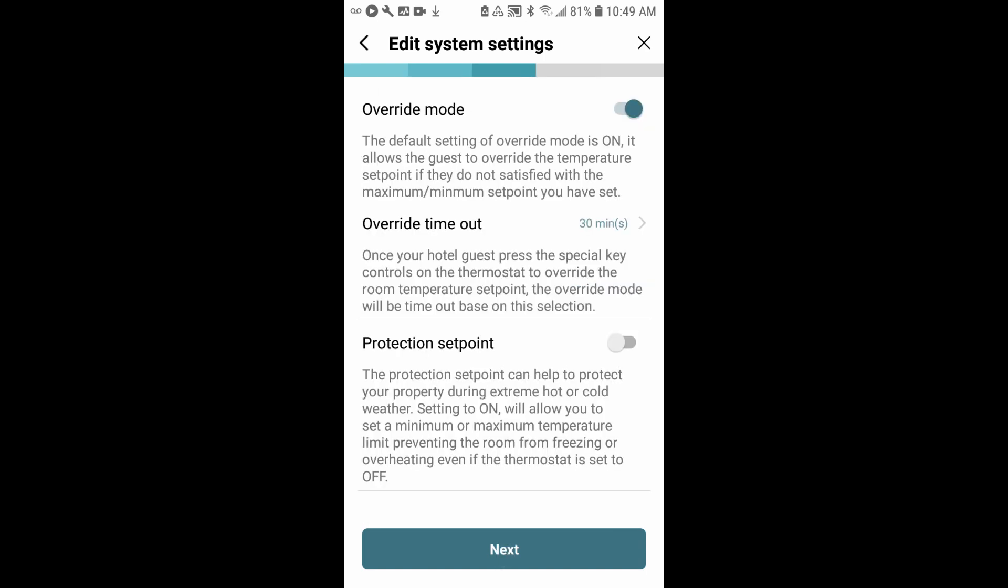Override mode is if you happen to have your temperature threshold set very tight - say that you'd set it 78 degrees and the guest wants it to 80 degrees - an override mode will allow them to press and hold an up or down arrow key to adjust the temperature. If they hold it for 3 seconds, it will go into override mode and allow them to adjust beyond your temperature threshold or your set points. The override timeout is how long will it allow it to override. So if the guest wants it set to 80, they can do that using the override, but it will only override for 30 minutes.